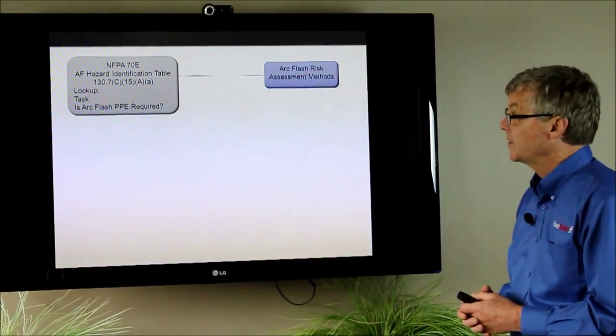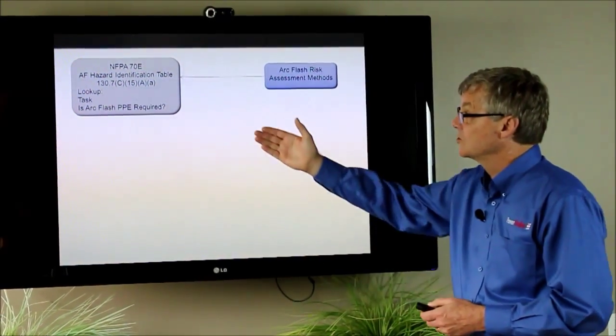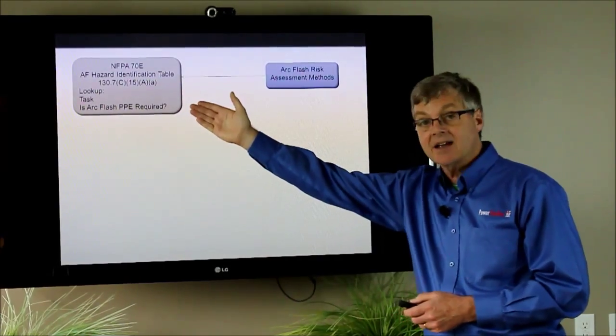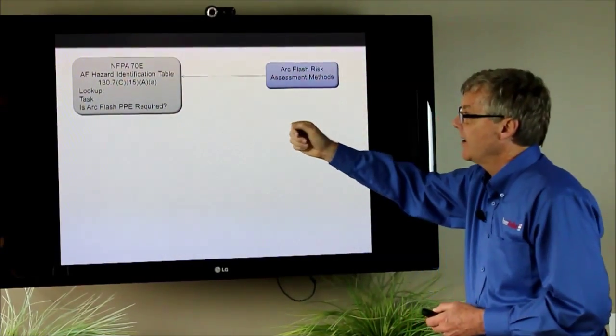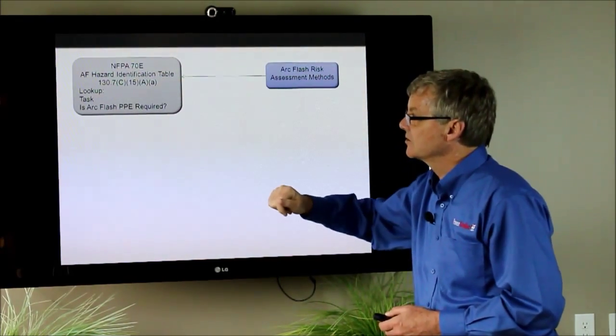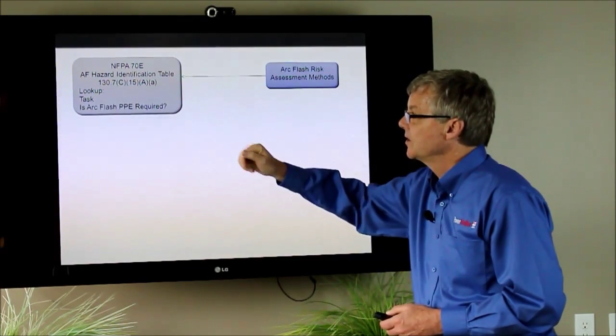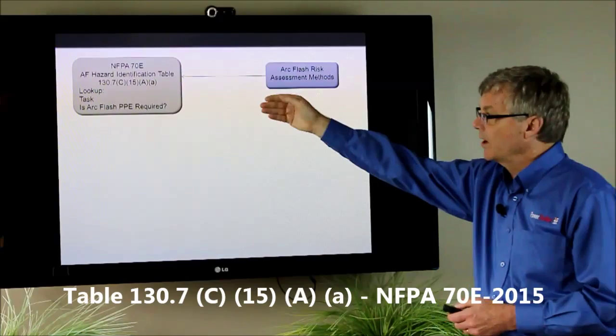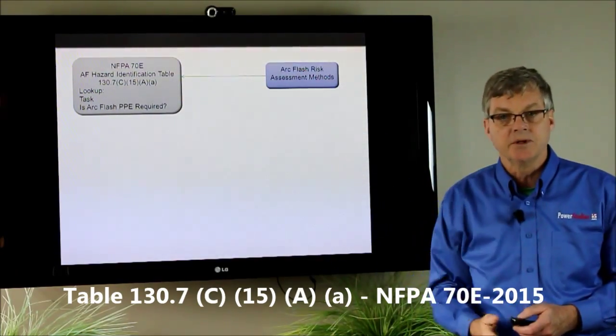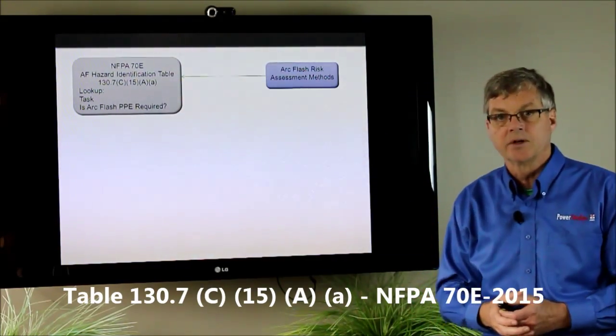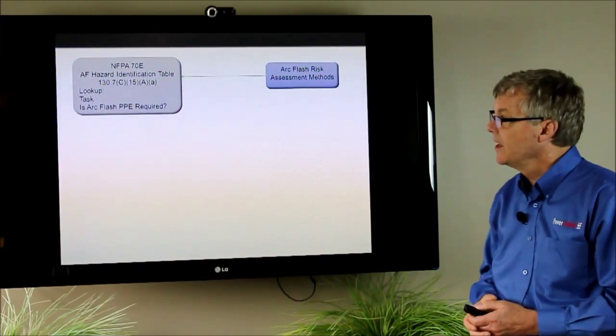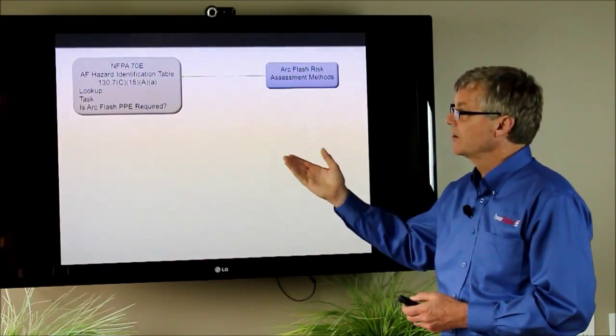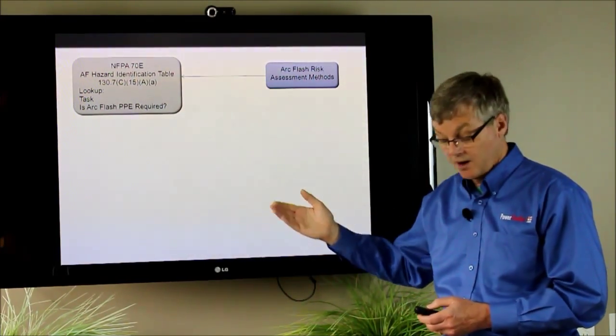One is to use the NFPA 70E task table method. They now have a new table in this 2015 version, 130.7C15AA, and that's where you look up the task that you're going to be doing, the type of job that you're going to be doing on a piece of electrical equipment, and then you look to see whether or not there's arc flash PPE required.